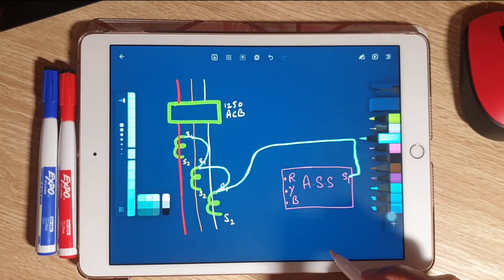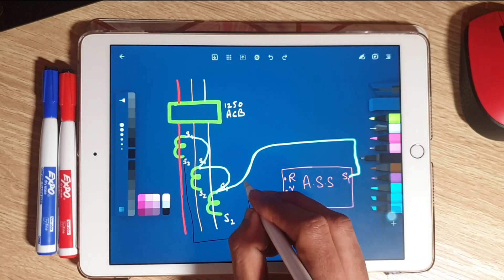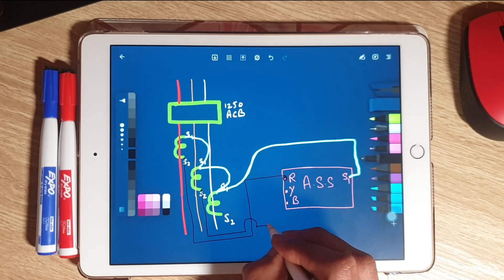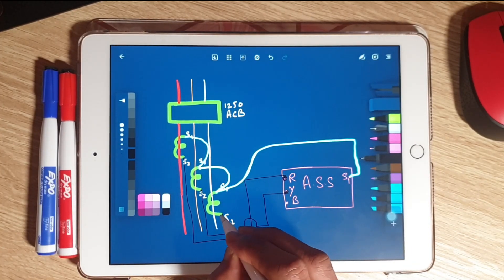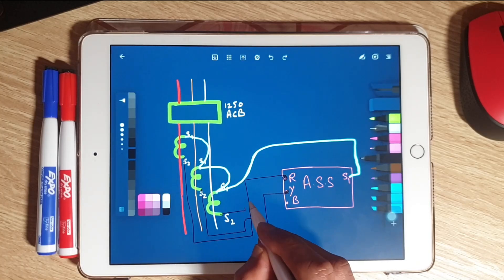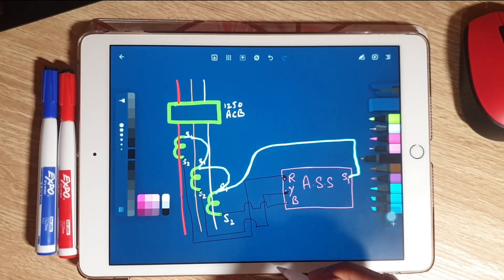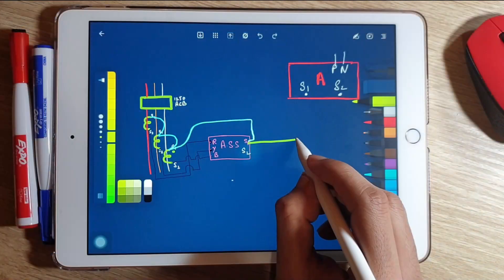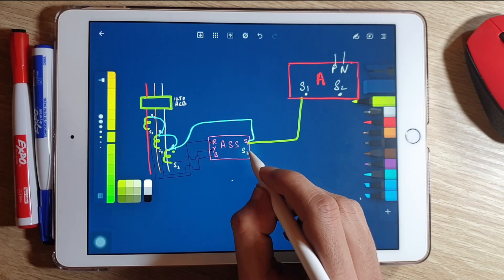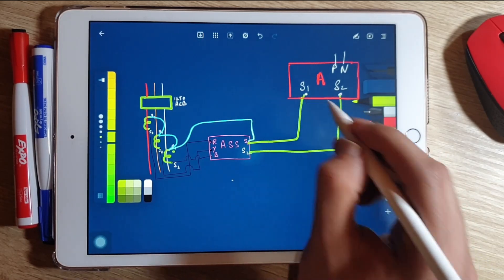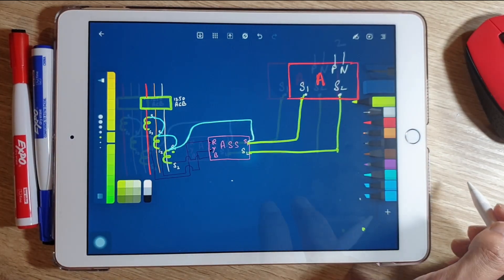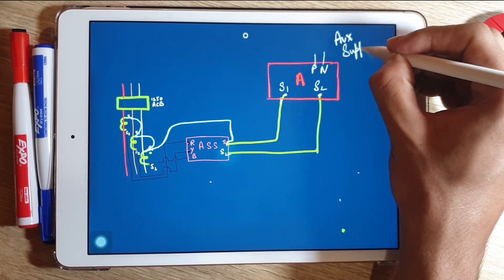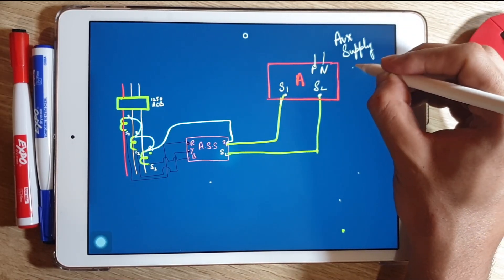The S2 terminal of the R phase CT is connected to the R terminal of the ammeter selector switch. Similarly, S2 of Y and B phase CTs are connected to the Y and B terminals respectively. The S1 and S2 from the ammeter selector switch are then connected to S1 and S2 of the ammeter, where P-N is an auxiliary supply of 110 or 230 volts.